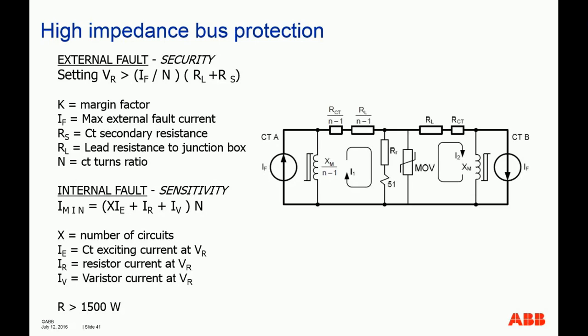Okay. So this is how to calculate the minimum operating setting. We also need to assure the sensitivity of this relay. Because there are so many CTs, as I mentioned, this is a group of CTs, and the current must also charge the excitation branch. You also need to flow through the resistor, and through the MOV. So you need the sum of all these together to estimate the minimum required current for this operating voltage VR, the current that is required in order for the scheme to operate. In other words, your fault current needs to be higher than this. That determines your sensitivity. Okay? So this is a very quick and easy introduction to high impedance bus protection.